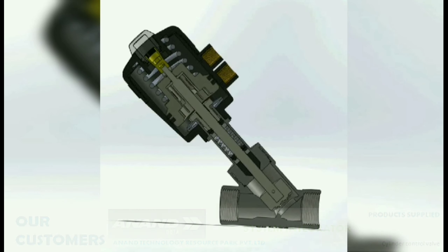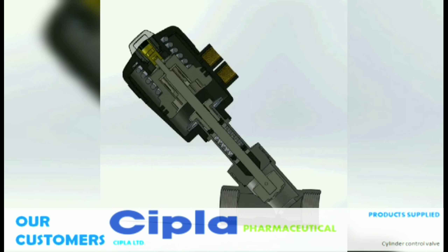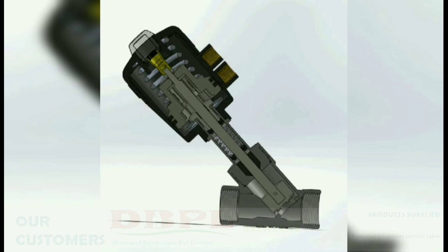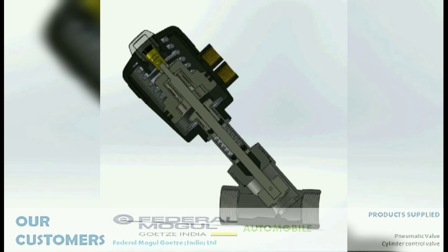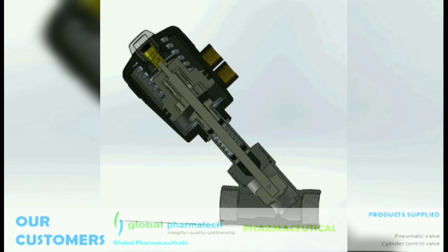This is how the valve operates. Pressurized air enters through the brass connectors and pushes the piston against the spring load. The piston then lifts the piston rod to raise the seal lap and open the valve. As the air pressure is released, the spring load acts on the piston and closes the valve to its initial position.